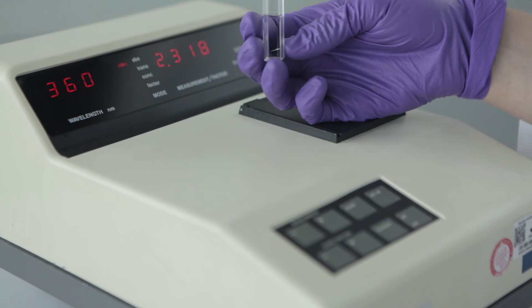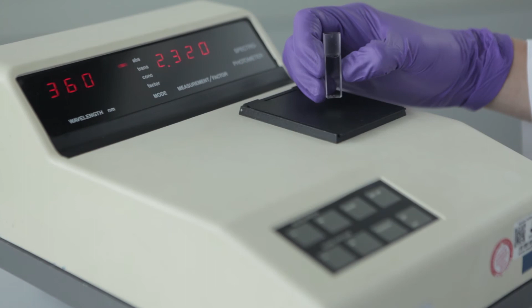A cuvette has two sides, a clear one and a ribbed one. We will make sure that the light will pass through the clear sides. It is very important that these sides are clean. So check for stains. We want to hold the cuvette only by the ribbed sides, so we don't leave our fingerprints. When all of this is correct, we will put the cuvette in the spectrophotometer.